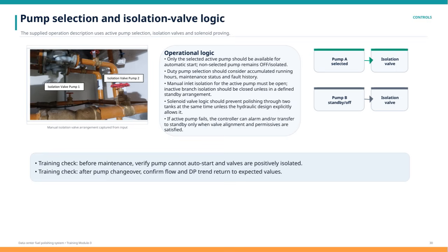The solenoid valve logic is designed to stop polishing fluid from passing through 2 tanks simultaneously unless the system's hydraulic design explicitly allows for that. If the active pump fails, the controller will raise an alarm and can switch to standby, but only once all valve positions and operational permissives are correctly aligned to ensure safe transfer.